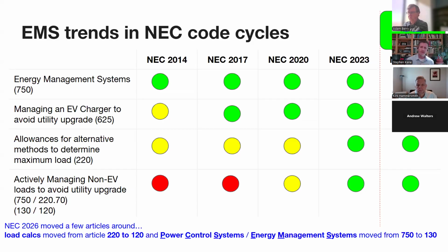So some solutions started being put into the code back in 2014, and as we've marched through time, the code has gotten broader each year in how we apply different loads to this scenario. As recent as the 2023 code, which we're currently under in Colorado, we can manage pretty much anything in the home. From a functional safety perspective, we have paths in Article 220.70 and 750 that let us size the system so we can manage loads and keep overcurrent protection from tripping.